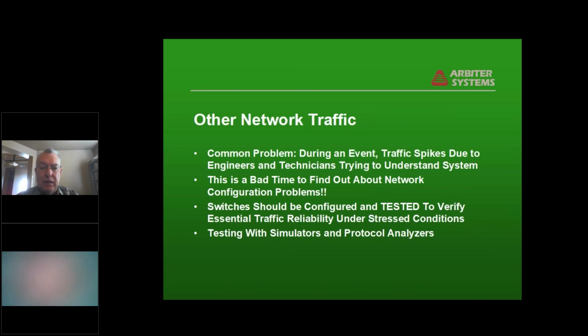The same applies to other network traffic, in other words, things other than just broadcast and multicast. For instance, during an event, traffic on the network will spike when people are trying to go on and download event records and find out what's going on. And as I say, that's a bad time to find out that your network's not configured properly. So again, the important thing is when you configure the switches and the IT people set it up, you need to actually test it under some simulated stress conditions. There are simulators and analyzers available to do that kind of thing.